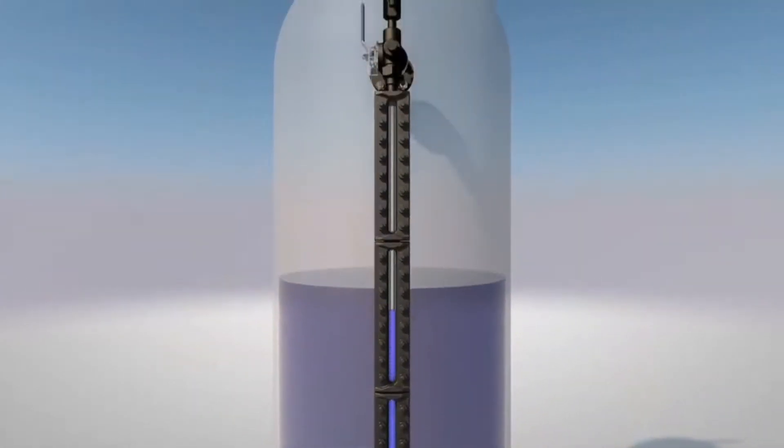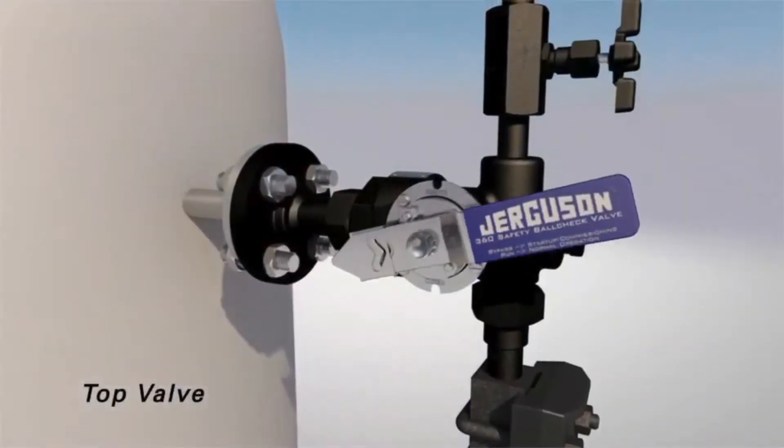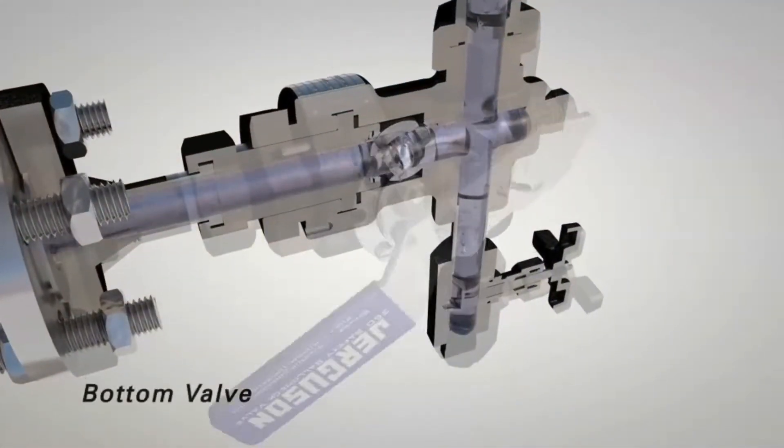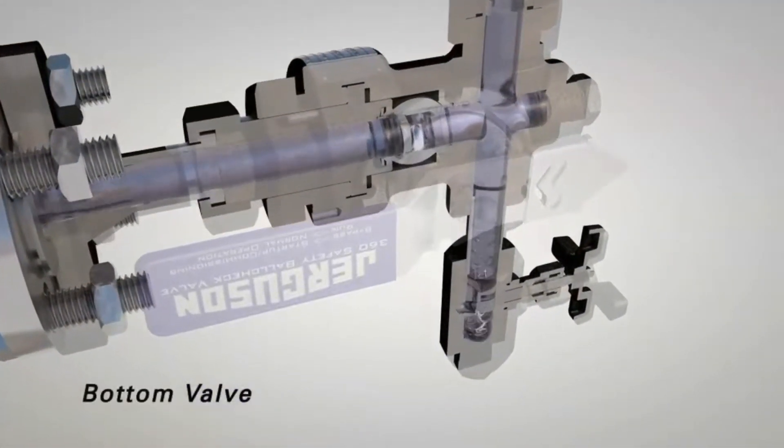Once the level stops rising, move the top valve to the run position then the bottom valve. The valve is now ready for normal operation.